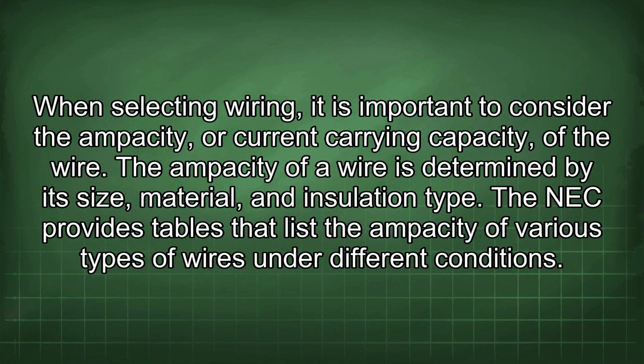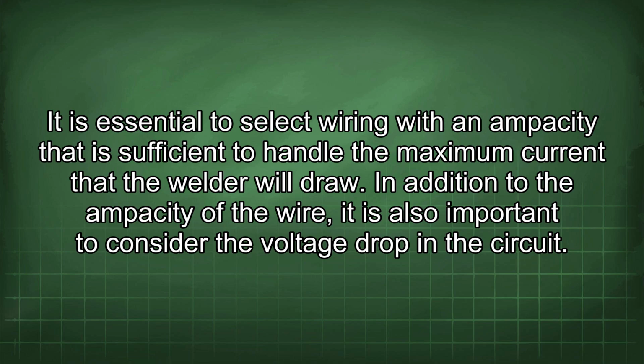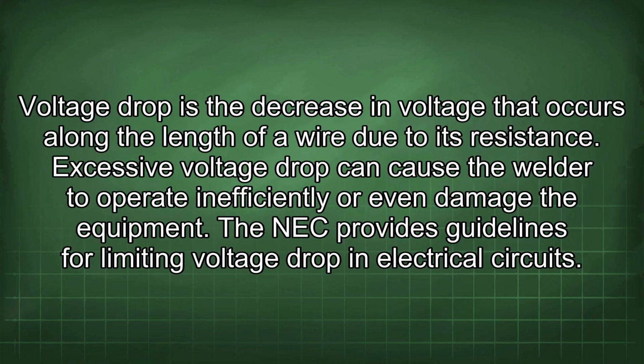The ampacity of a wire is determined by its size, material, and insulation type. The NEC provides tables that list the ampacity of various types of wires under different conditions. It is essential to select wiring with an ampacity that is sufficient to handle the maximum current that the welder will draw. In addition to the ampacity of the wire, it is also important to consider the voltage drop in the circuit. Voltage drop is the decrease in voltage that occurs along the length of a wire due to its resistance. Excessive voltage drop can cause the welder to operate inefficiently or even damage the equipment.